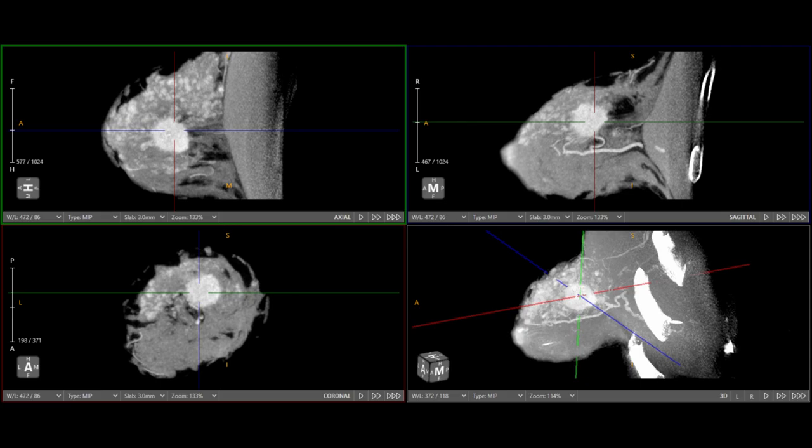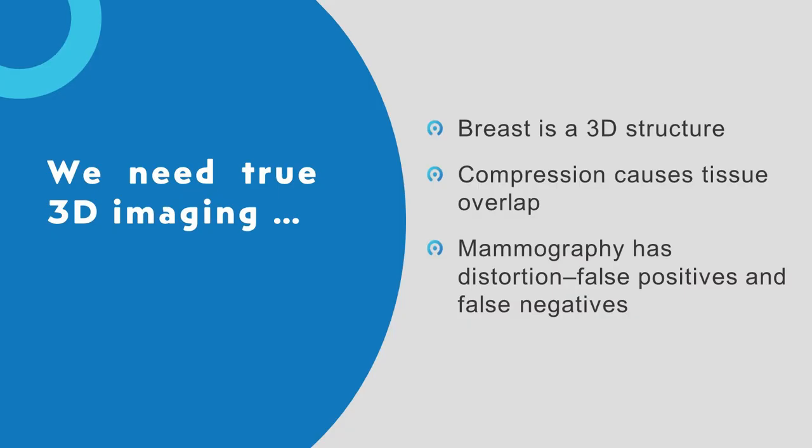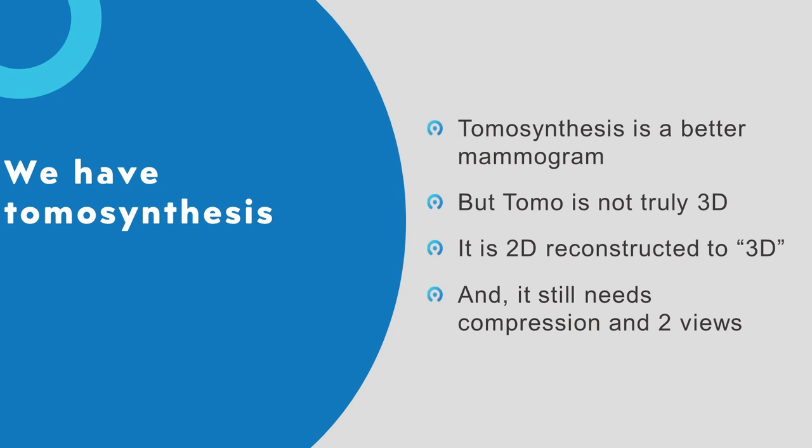Moving on — true 3D. The breast is a 3D structure, and compression makes it into a 2D. Tomosynthesis is not really 3D — it's a reconstruction into 3D, a pseudo 3D, so it can't have perfect resolution in all planes. From the technical point of view, tomo is 2D reconstructed to 3D. It still has compression and two views per side. But no question, it's a better mammogram.